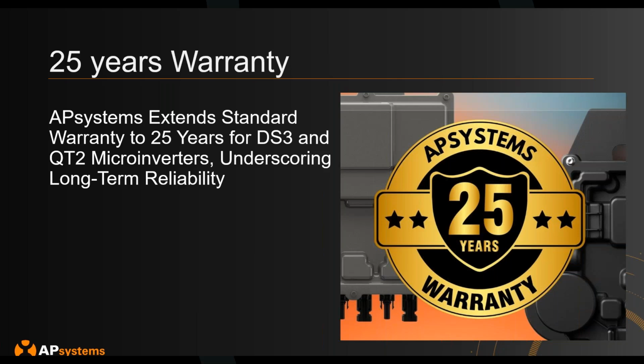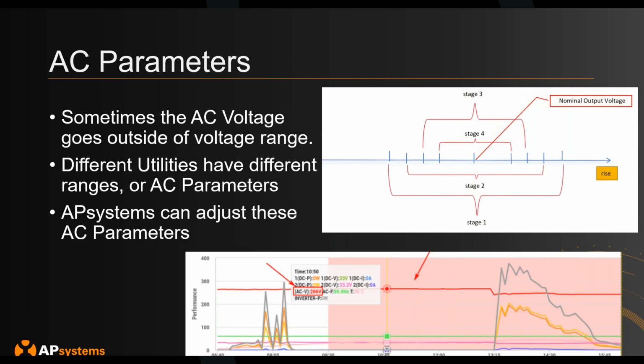This is an interesting side point, and probably one of the most common issues we run into in the field: people often think the microinverter is performing incorrectly or having problems, but in reality it's actually a setting required for compliance with grid regulation. Let me describe this phenomenon.